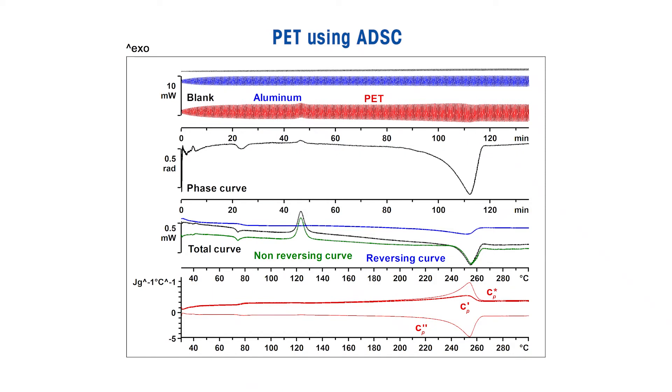Starting from the top, this evaluation shows a blank curve, calibration with aluminum and PET sample curves. The ADSC evaluation computes a phase curve, total reversing and non-reversing sample curves, and the complex heat capacity curve. The enthalpy relaxation is observed in the non-reversing and total heat flow curves. The reversing curve shows the glass transition without an enthalpy relaxation peak. The peak due to cold crystallization is only observed in the non-reversing and total heat flow curves.